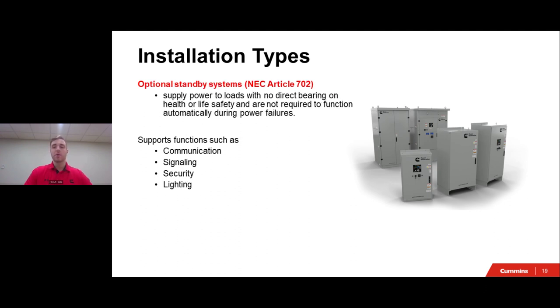Lastly, we have the optional standby systems. Optional standby systems supply power to loads with no direct bearing on health or safety and are not required to function automatically during power failures. They are typically found in commercial buildings, farms, and even residences, and must meet the requirements of Article 702 of the National Electric Code, once again known as NFPA 70.